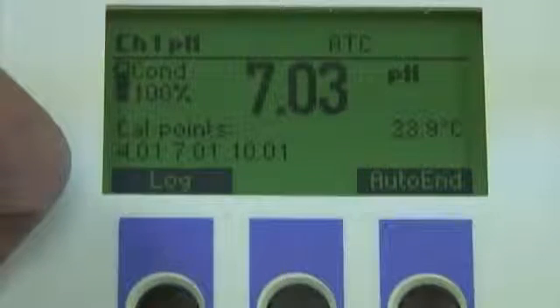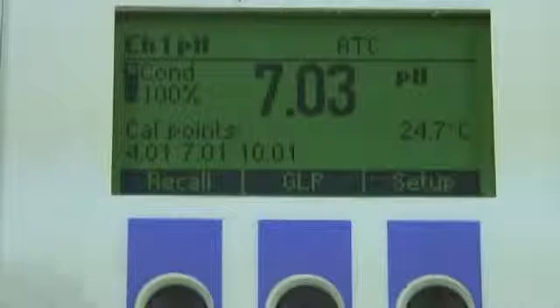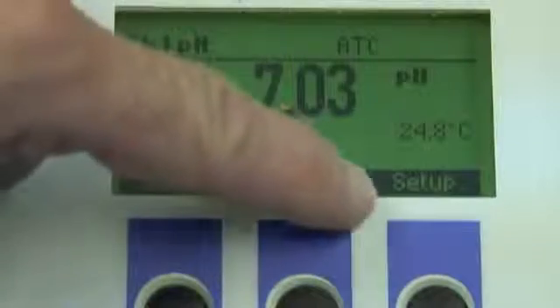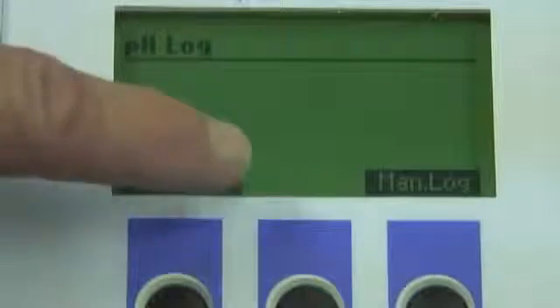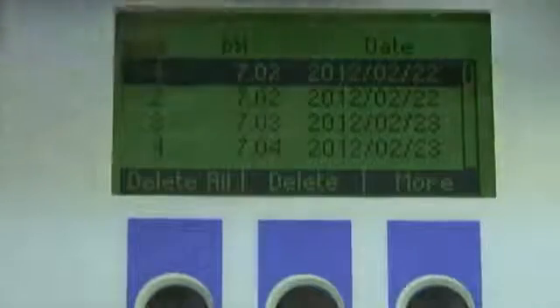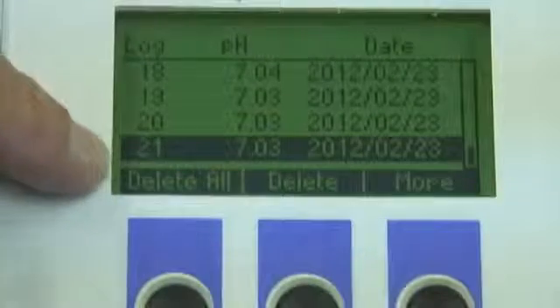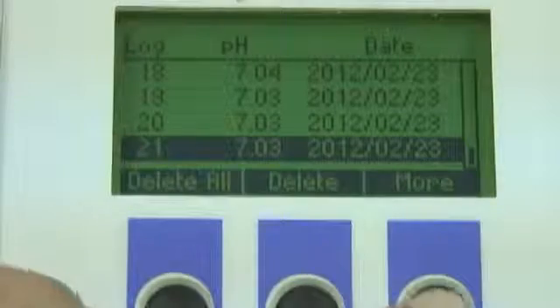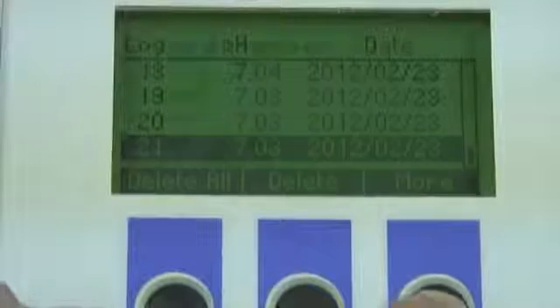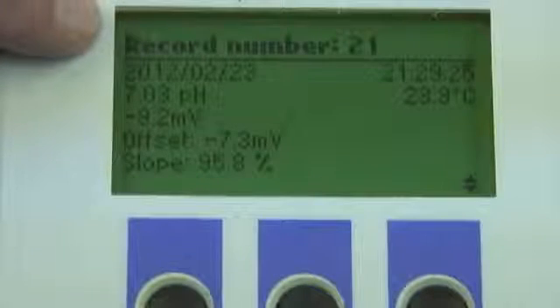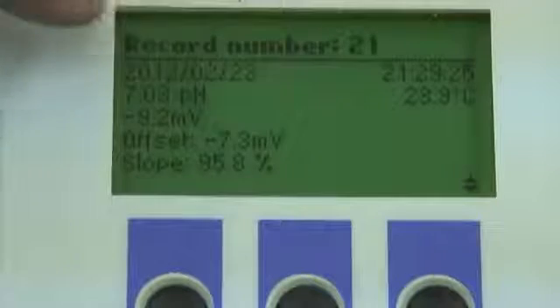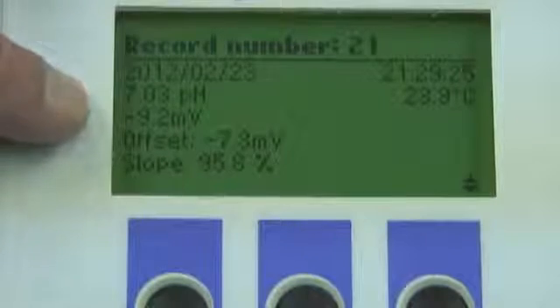Next, let's hit the menu button. The virtual keys have now changed. We see the recall button, GLP, and setup. I'm going to hit the recall button and I see two different options, auto log and manual log. And since my last record was done manually, I'm going to hit the manual log and I'm going to find the log, and in this case it's log number 21, which shows the pH and the date. If I want to see even more information, I hit the more button. We see again this is record number 21.